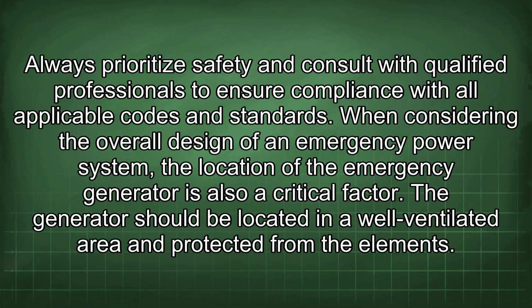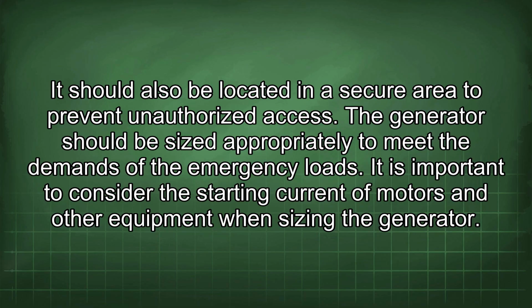When considering the overall design of an emergency power system, the location of the emergency generator is also a critical factor. The generator should be located in a well-ventilated area and protected from the elements. It should also be located in a secure area to prevent unauthorized access. The generator should be sized appropriately to meet the demands of the emergency loads. It is important to consider the starting current of motors and other equipment when sizing the generator.